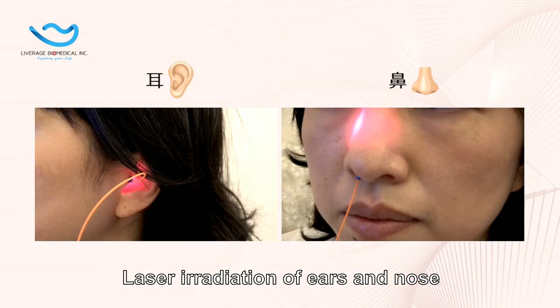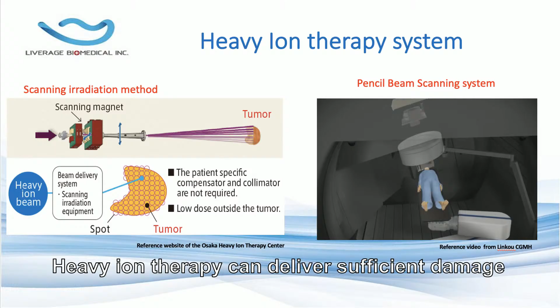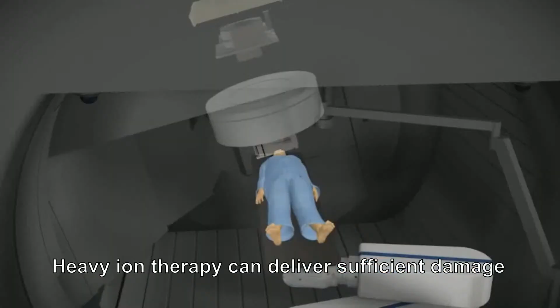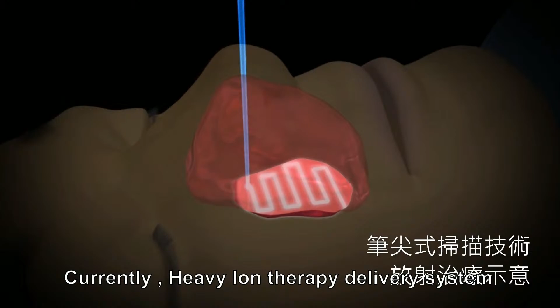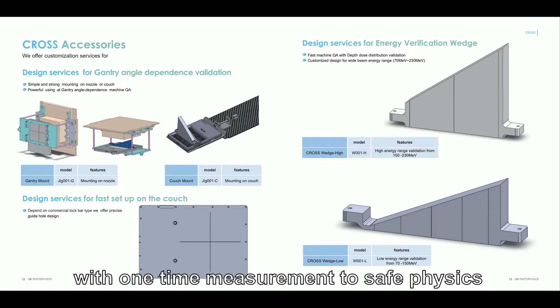For photophysics, we have the CROSS series and Wedge series. Heavy ion therapy can deliver sufficient damage to the target cancer while minimizing damage to healthy tissue. The heavy ion therapy delivery system is called PBS, pencil beam scanning system. Our product suits pencil beam scanning system machine quality assurance, including beam position and spot size variation, beam scanning speed variation, beam energy variation, and dose deviation. Our product's advantage is that it can measure all items in one measurement, saving pencil beam scanning system QA time. Our advantage is also easy and short setup, with 3 minutes to finish all setup.